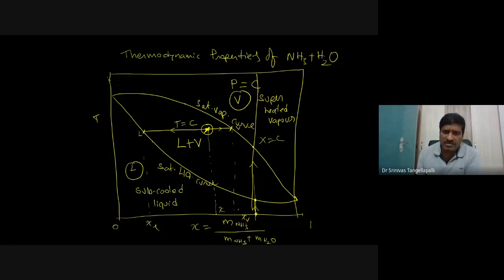In the evaporator, what is happening? I am showing the complete evaporation process in this property chart. If it is a single fluid system, there is no such loop. Only one line will be there. The boiling starts at this saturation temperature. So this entire curve we can call the saturation line, the bubble point line.